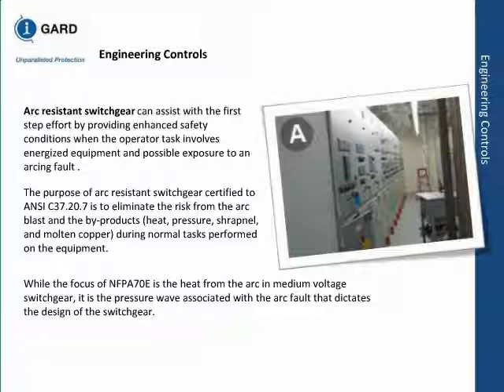Of course, when the fault happens, the inside of the arc-resistant switchgear may or may not be in workable condition. It may have to be rebuilt or repaired or something to that effect. Also keep in mind, arc resistant is only arc resistant when the doors are closed. When the doors are open, the property is not available.